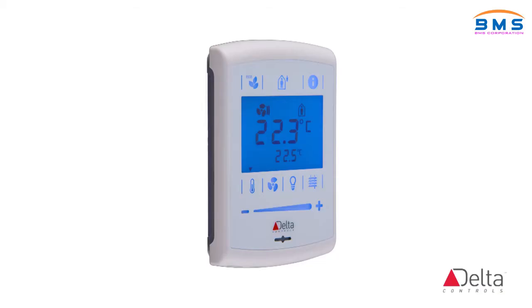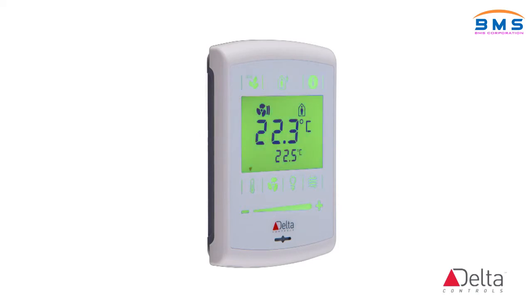It supports a network stat, either a DNS or an eZNS, and all of the various input options you can get with either of those. So your temperature, humidity, motion, and CO2. With the new eZNS sensor, one of the neat things that the algorithm does is it also makes it easy to configure the stat for all the various button and Mylar combinations that you can get with the new eZNS sensor without having to go to custom GCL programming.